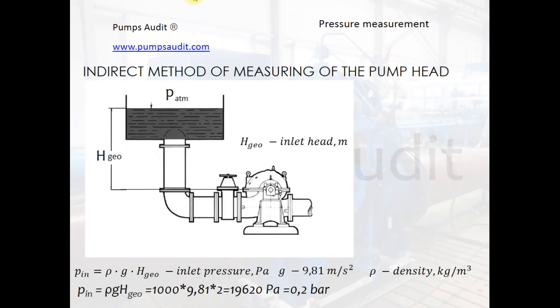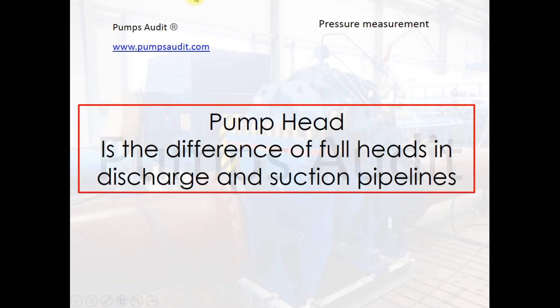Very often pressure gauges are absent and there is no direct opportunity to measure pressure. But sometimes you can use indirect methods for evaluation of pressure. For example, if the pump takes liquid from a tank, the level of the liquid in the tank can be converted to pressure using a formula. It is important to remember that pump head is the difference of full heads in the discharge and suction pipelines. Very often pump users forget this and do not install a pressure gauge in the suction pipeline, which can lead to incorrect pump head evaluation.